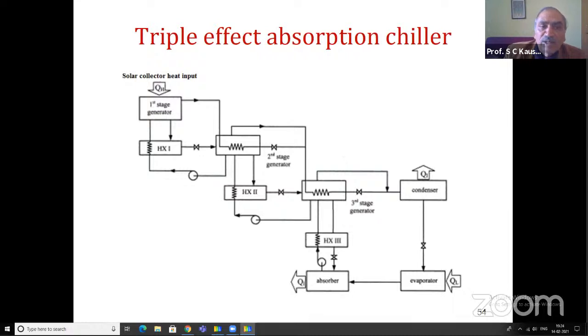This is the triple effect absorption chiller. You can see at first stage, then second stage, and then third stage. Same principle as we have used for the double effect. Similarly here, the triple effect, and we can provide higher COP, you can say nearly thrice as compared to the single stage system.